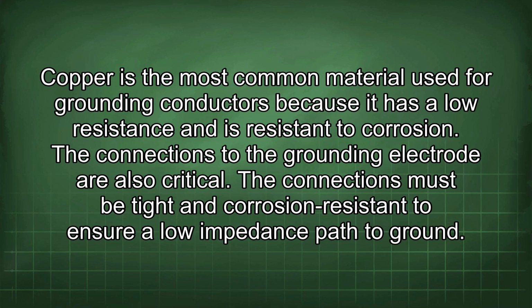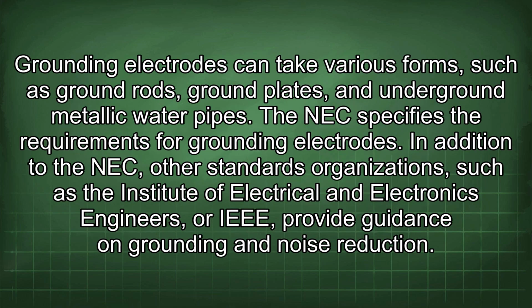The connections must be tight and corrosion resistant to ensure a low impedance path to ground. Grounding electrodes can take various forms such as ground rods, ground plates, and underground metallic water pipes. The NEC specifies the requirements for grounding electrodes. In addition to the NEC, other standards organizations, such as the Institute of Electrical and Electronics Engineers, or IEEE, provide guidance on grounding and noise reduction.